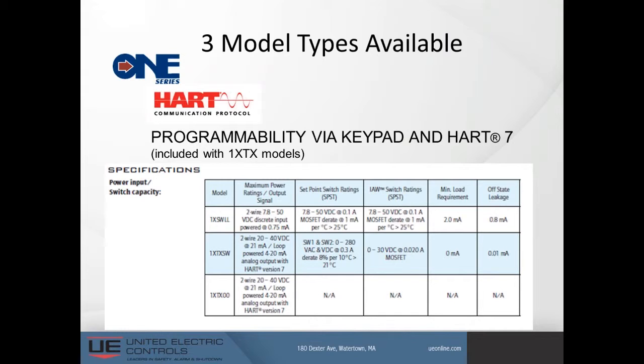So once again, you could go into this just like a transmitter. It does not have a 10 to 1 turn down, it's just got a 2 to 1 turn down, trying to keep the cost in check. Through HART, you can set your DDs, you can put an address into this, and it also again has diagnostic capabilities. So plug port is in there, and all your IAW scenarios are in there as well. So HART is here. We have it. And those are the three models as they exist currently.